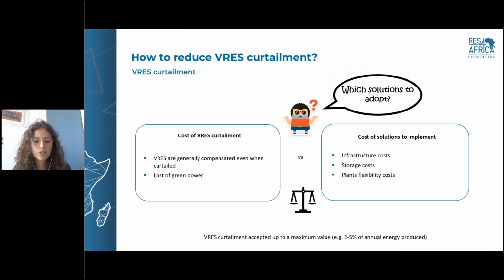increase the penetration of renewables without increasing curtailments if you take the proper countermeasures. So what to do is, of course, as always, a compromise. RES curtailment has a cost, because basically we are installing something that we are not using, and we are losing free energy, that is the green power. Also, the majority of regulations, for example in Italy, compensate the energy curtailed. So if the TSO, if Terna, needs to cut the production of renewables, it needs in any case to pay for that energy that is not being sold. So it's a cost. But the solutions to implement are also costly if we are speaking about infrastructure, storage systems, increasing flexibility of plants. So what to do is a compromise, choosing which is the most convenient thing to do. Generally, curtailment is accepted up to a certain level, around 2-5%. After that, some countermeasures should be put into place.